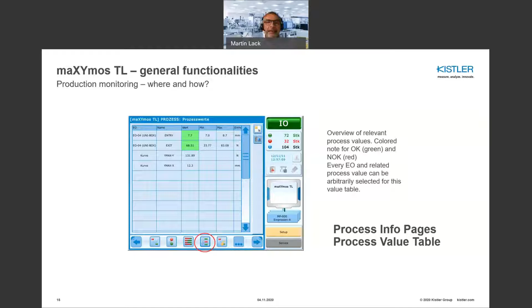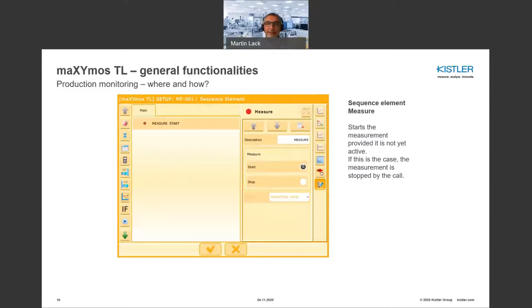Another point the maXYmos TL can do in general is a sequence functionality, which we call sequence mode. This works like an easy PLC functionality, so you can enter a small program related to your inputs and outputs. You can control the function of the maXYmos by these digital IOs, or give the operator messages related to your process, for example when a force is exceeded, or when a digital input occurs and the worker has to change something, or you can give the operator the actual measuring values back via this sequence element.